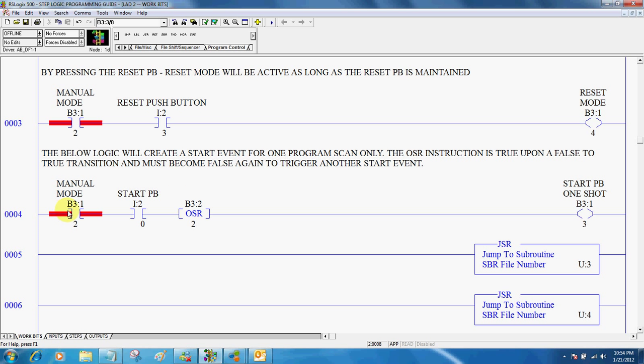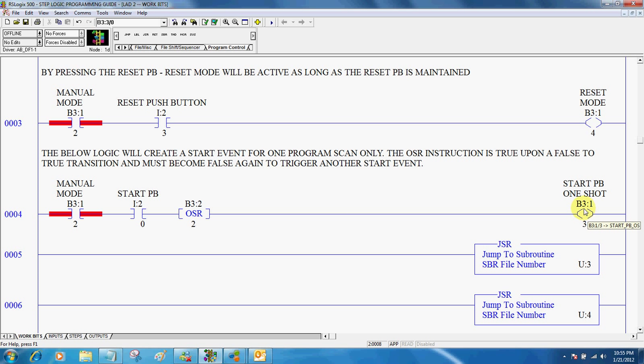One thing that we're going to need in our program is called a one shot bit. A one shot is true for one program scan only. So if this instruction is true and this instruction is true, the one shot rising bit becomes true for one scan only. This will typically happen so fast that you'll never see it come true in your program.